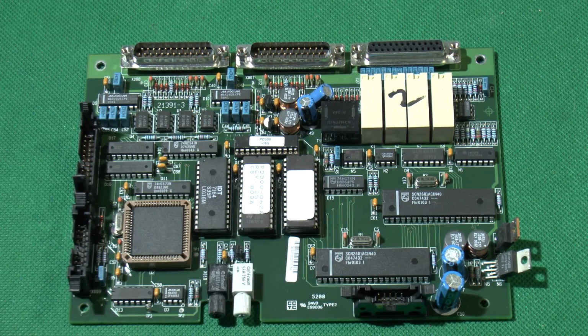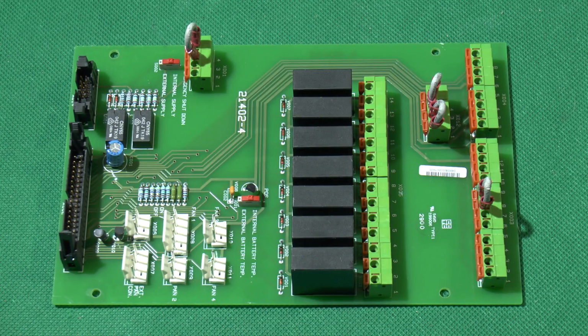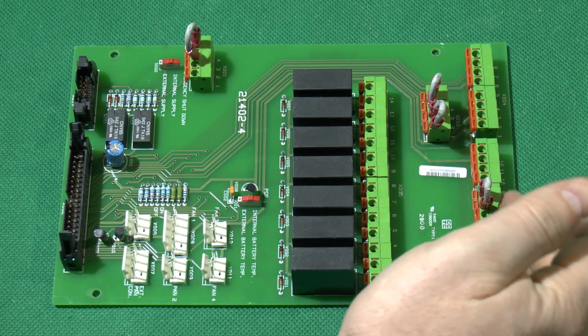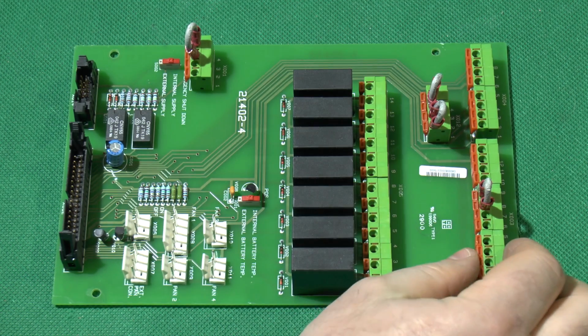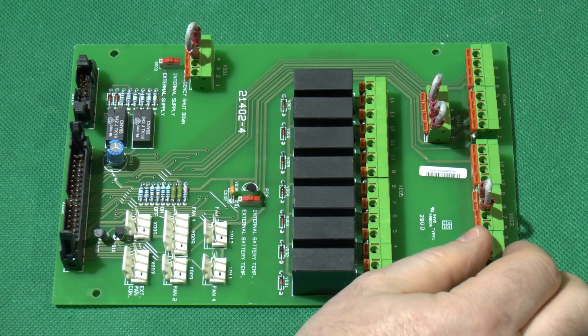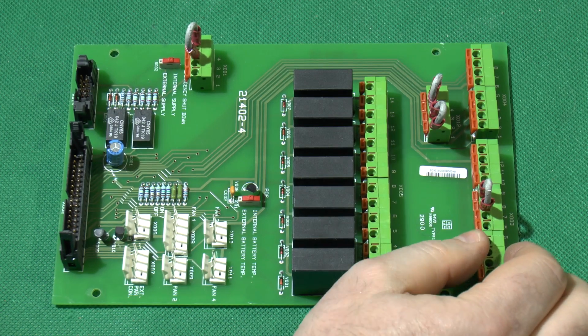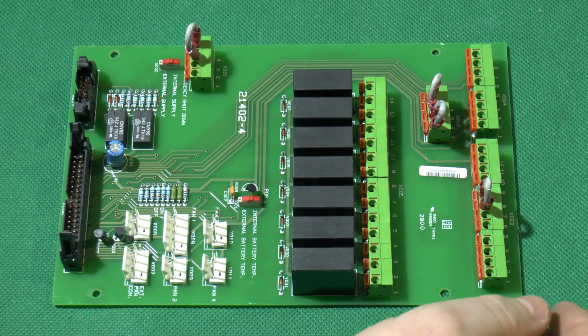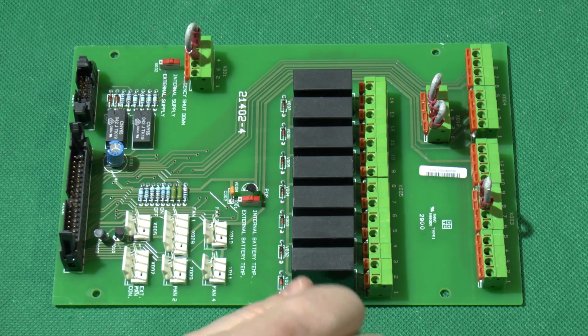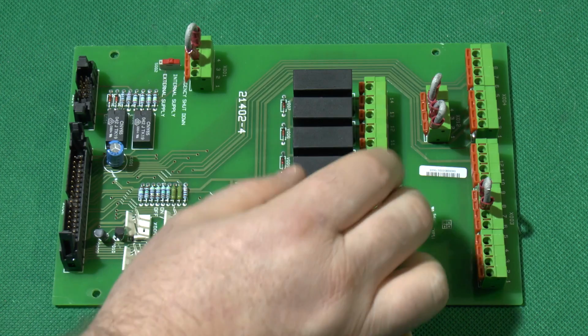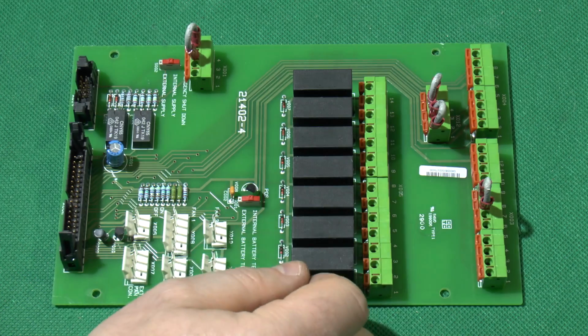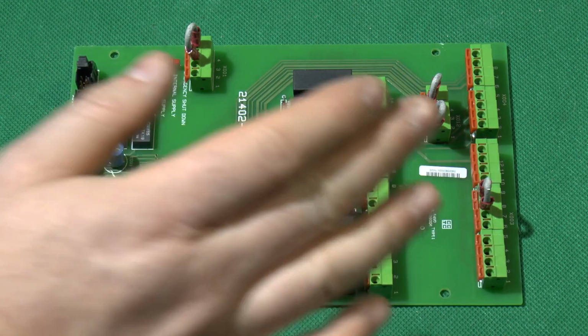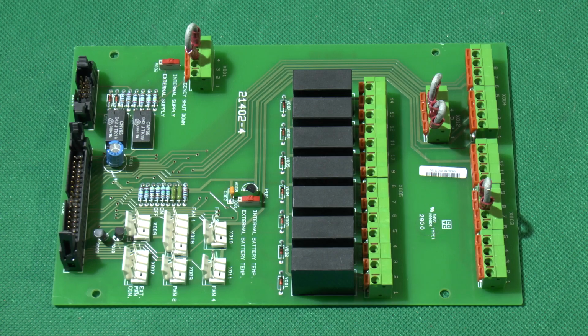And just above this board we have this board. This board connects off to the status indicators and contacts on the bypass panel, the rotary switch bypass panel. On a Silcon bypass panel, it's got indicator LEDs which indicate when you turn the bypass, when you put it into bypass, you'll get an indicator light indicating by the bypass switch that it's now okay to turn that. When you turn that, you get indicators on the other light switches to say it's now safe to turn these.